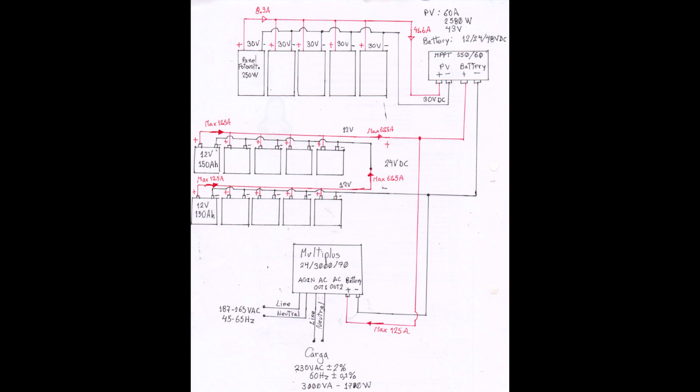The batteries, 10 batteries, each one with 12 volts and 150 ampere hour. Configure this with series and parallel connections to get 24 volts direct current.